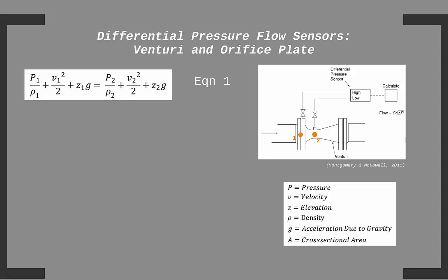In the equation shown here, the P's are pressures at state 1 and 2. The V's are the velocities at the two locations. The Z's are the elevations of the respective locations. G is the acceleration due to gravity, and rho is the fluid density. When you place a flow sensor in a stream of an incompressible fluid, like the Venturi flow sensors here, the density can be assumed to stay constant, and there would be no change in elevation. Thus, the equation can be simplified to equation 2, shown here.